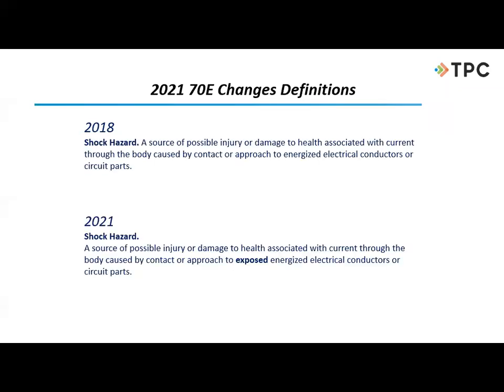Shock hazard also came into play as a change. They put in the word exposed, because the technical committee believes that if the equipment has all the covers on, no openings, and we cannot reach into where those energized parts are, then there is no shock hazard. We should all remember that if electrical equipment has been maintained and installed properly, with all covers on and no evidence of impending failure, then there are no hazards. We should be able to walk past that equipment in the course of a day and not be exposed to a hazard.